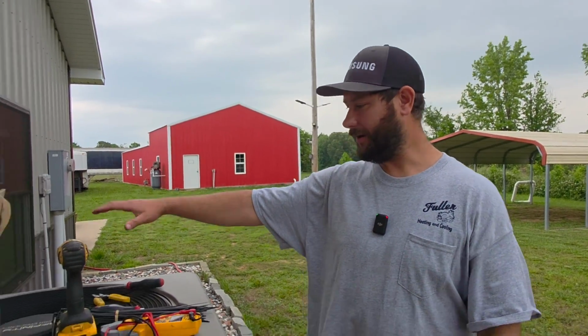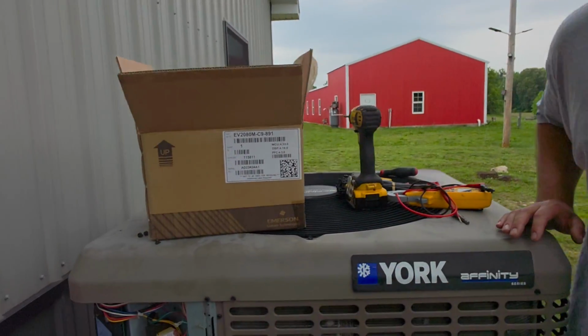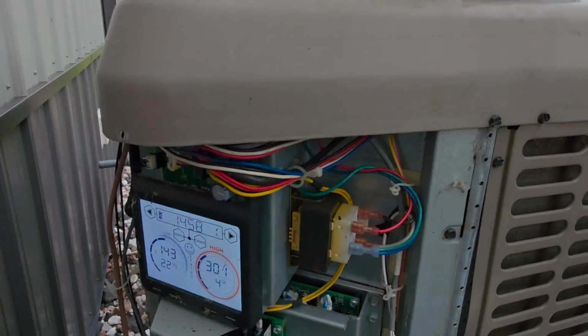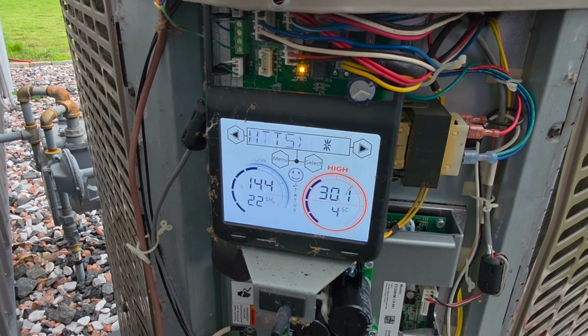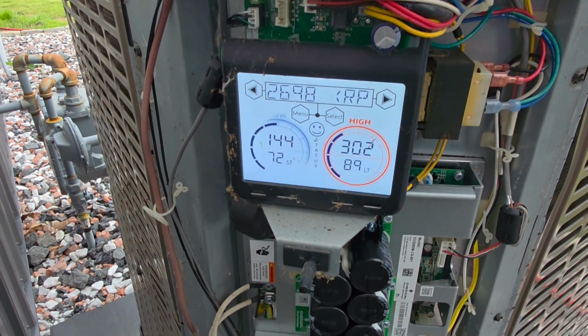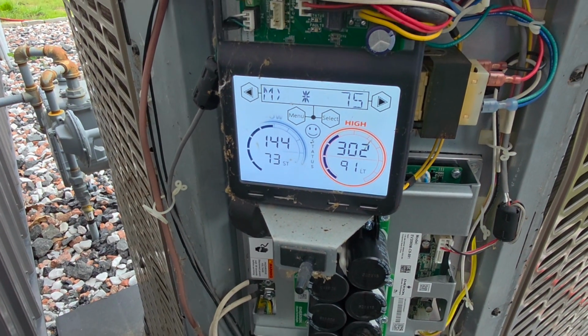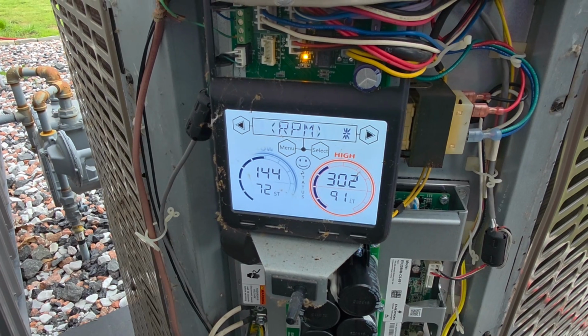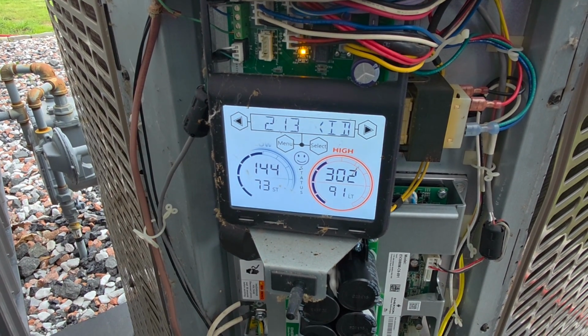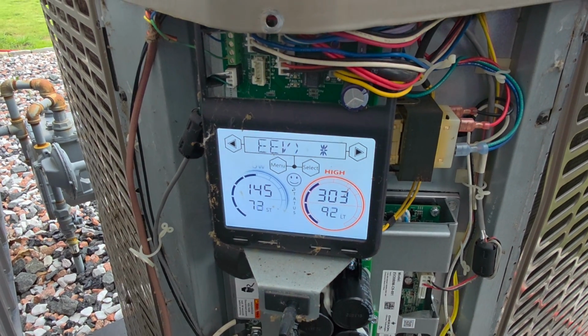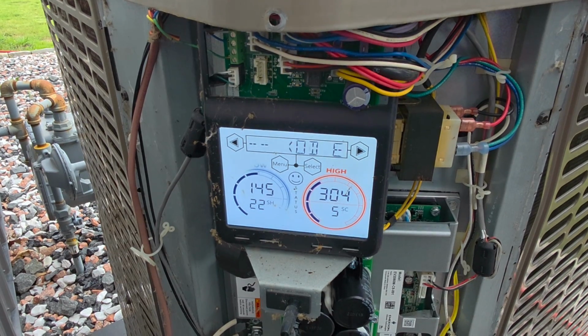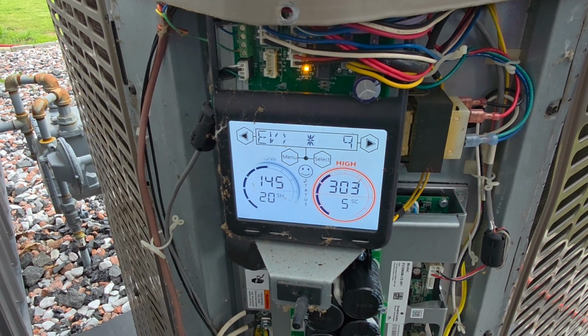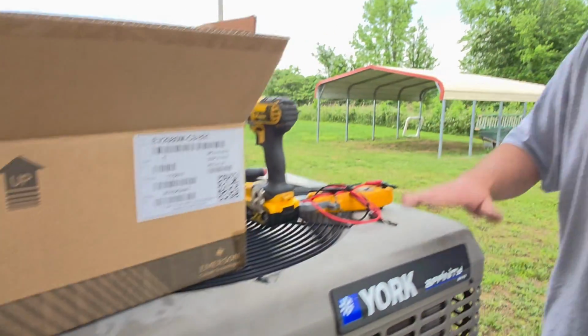So we got air, equipment's running. Let me show you this little board here. You can see the pressures, 140 on the low side, 300 on the high side, and then we've got our liquid line temperature, suction line temperature. So it's working, I love it. We got all our status, 22 degrees of superheat, 5 degrees of subcooling.